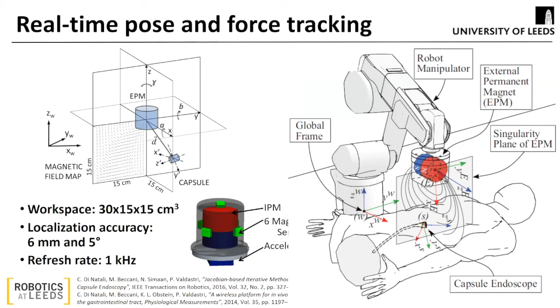This method was proven successfully in the target workspace, with the only exception of a singularity plane in the center of the external magnet and perpendicular to its main axis. There, the magnetic field is always the same, and the position of the magnetic endoscope cannot be discriminated. For this reason, we had to introduce a coil perpendicular to the external permanent magnet, as you can see here. And this coil creates a field that is different at any point in the singularity plane, allowing us to identify the position of the magnetic endoscope.